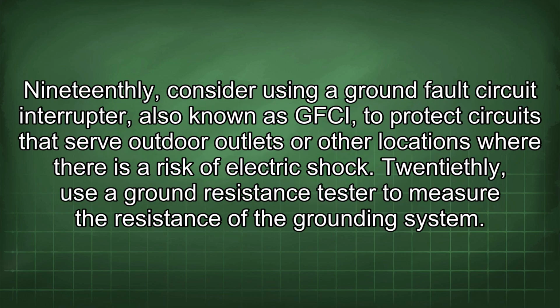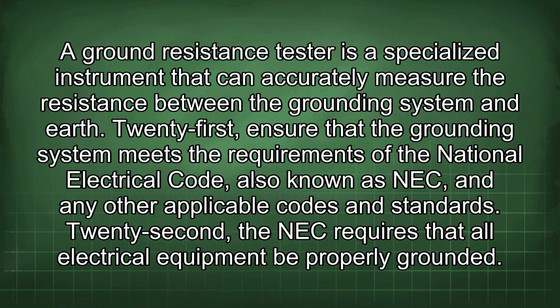19thly, consider using a ground fault circuit interrupter, also known as GFCI, to protect circuits that serve outdoor outlets or other locations where there is a risk of electric shock. 20thly, use a ground resistance tester to measure the resistance of the grounding system. A ground resistance tester is a specialized instrument that can accurately measure the resistance between the grounding system and earth.